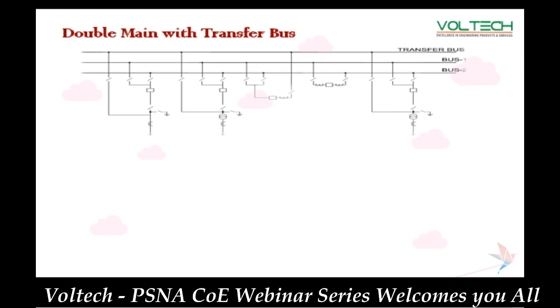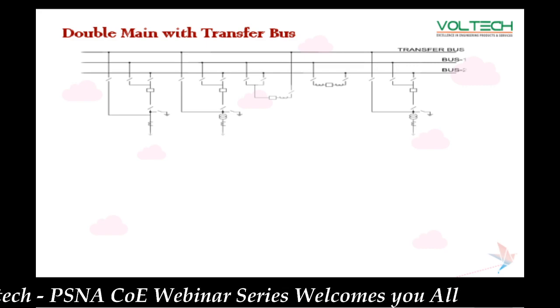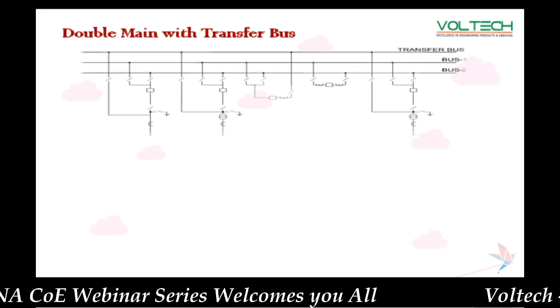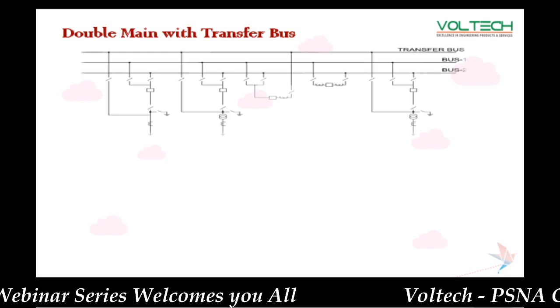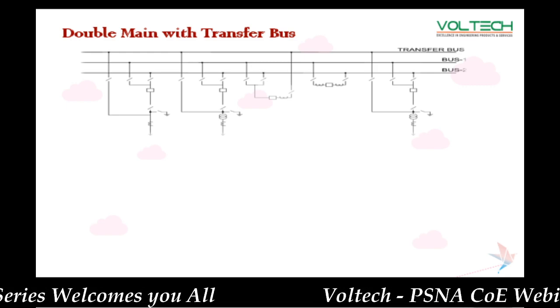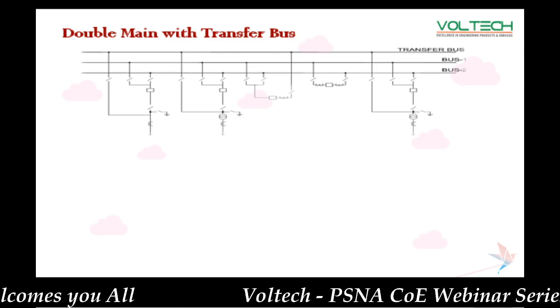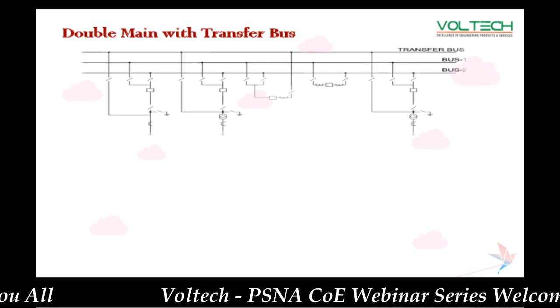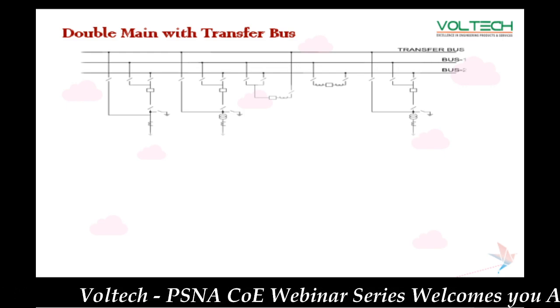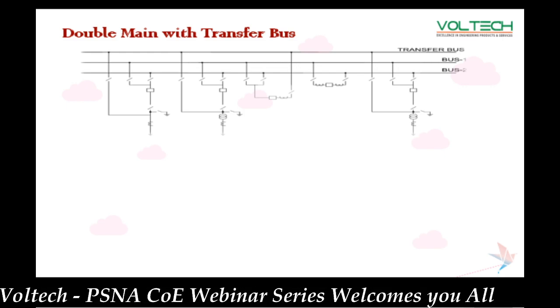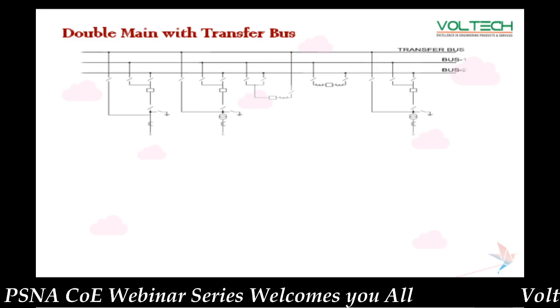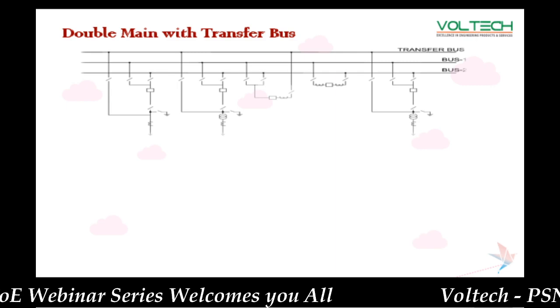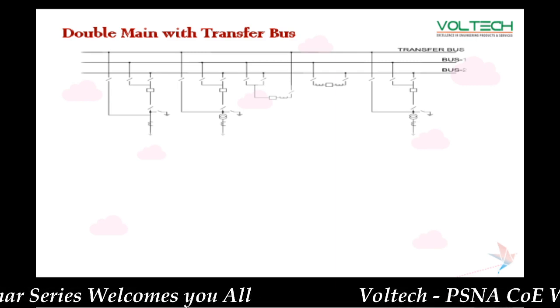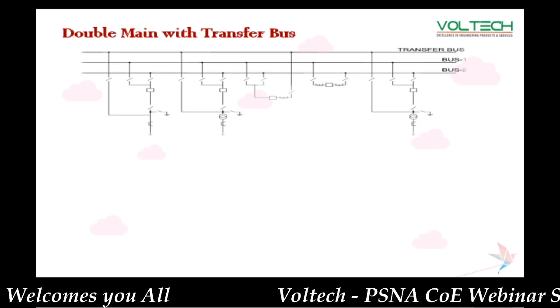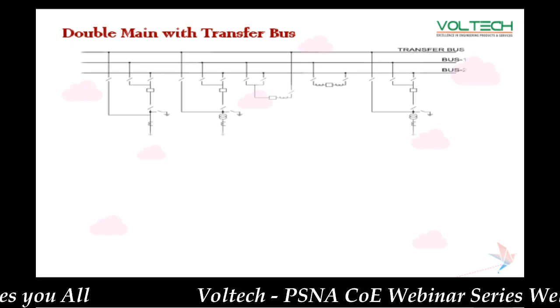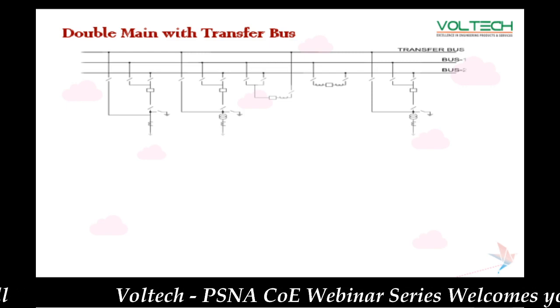There is only one common breaker here, connected to the bus bar, and there are isolators. If I want to transfer power from bus 1 to bus 2, I can close this isolator and it will transfer to bus 2. During maintenance, if I want to maintain the substation without shutting anything down, I can remove these two buses. The power coming here, I open this isolator and at the same time close this one, so power flows directly to the transfer bus, which is now energized.